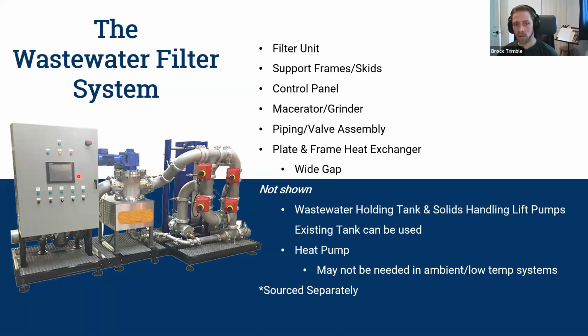This style is usually used in large applications where there's a lot of wastewater flow, typically 300 to 400 or even more units. I've seen one of these systems, not paired with geothermal, used effectively for standard wastewater energy recovery in a 700-unit multifamily project in Vancouver, BC. This type of application, and the smaller-scale version, serves a broad range of multifamily buildings, and the energy recovered can be put back into the building or into the geothermal source to provide supplementation.